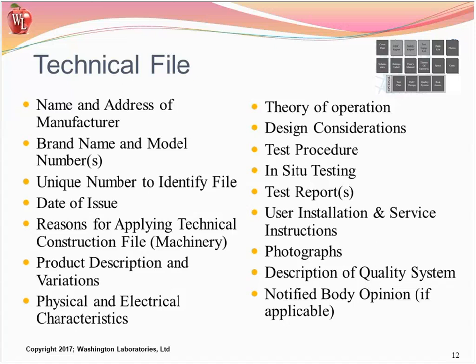You may need to take care of a test procedure or in situ, on-site testing, where things are not done in conformance with the standard, because the standard says use the harmonized standard, and that's never an in situ case. So you'll always get involved with having a notified body opinion associated with in situ testing.